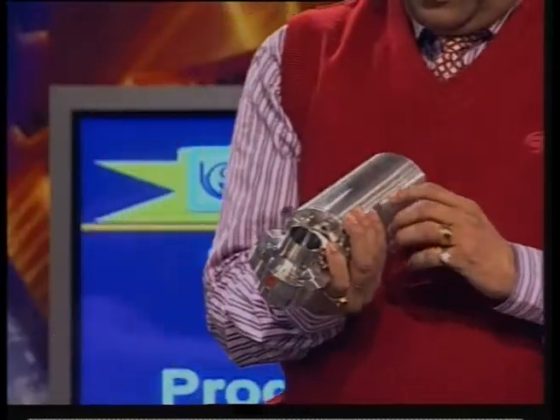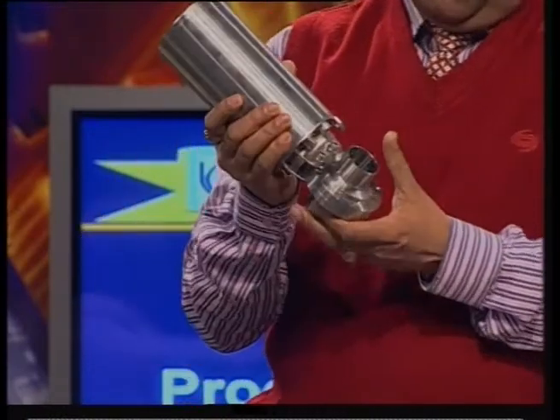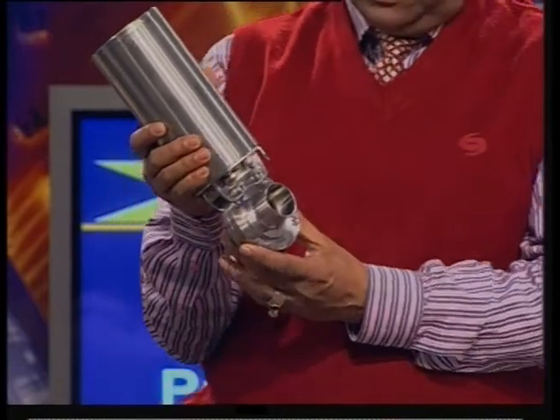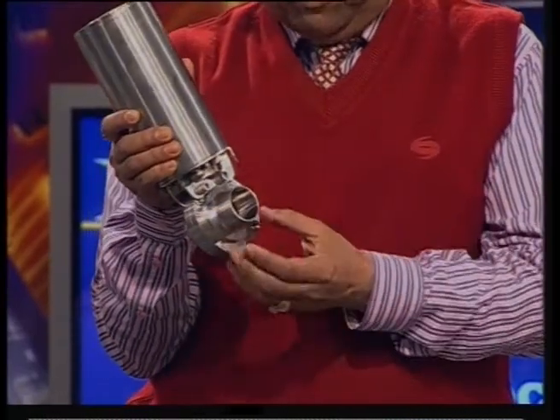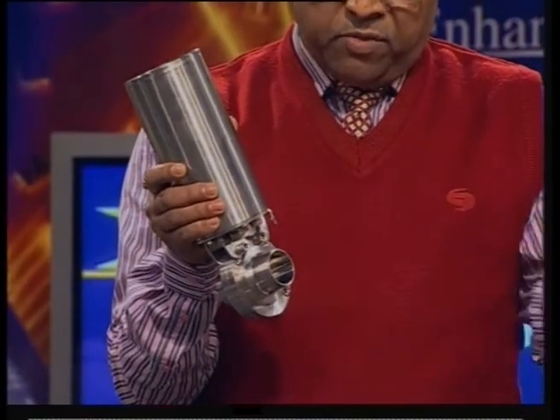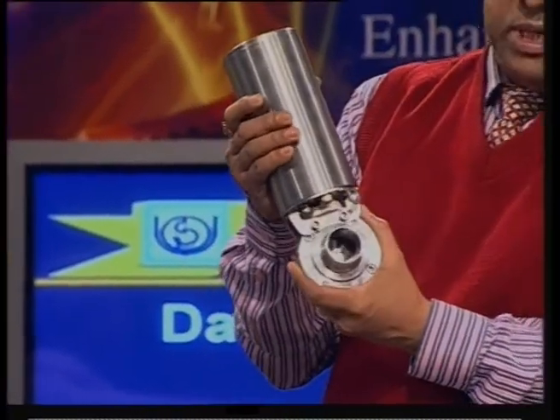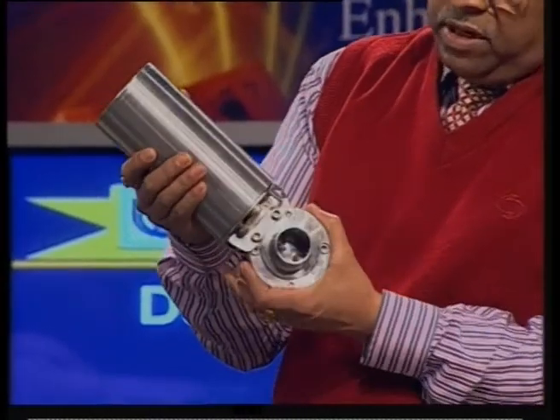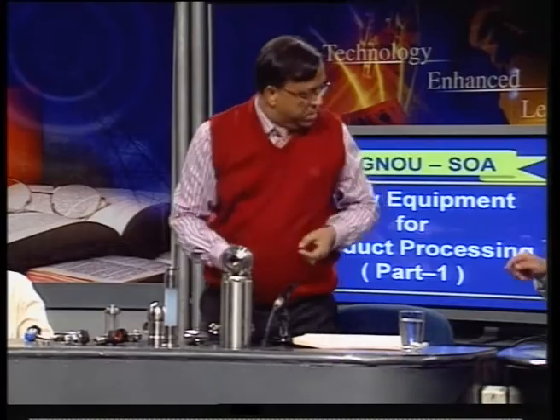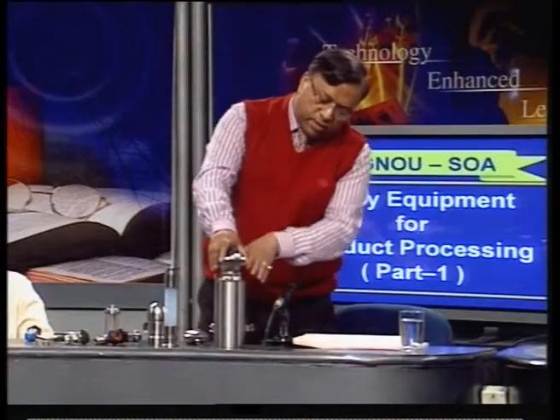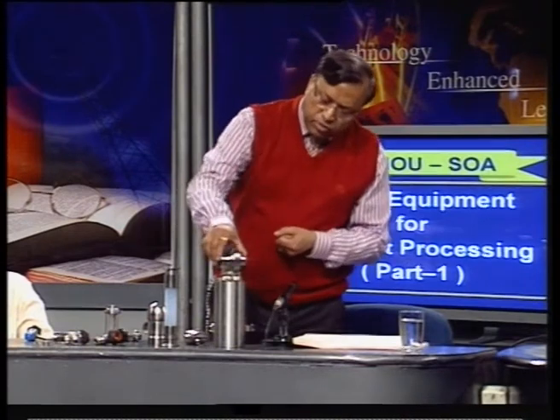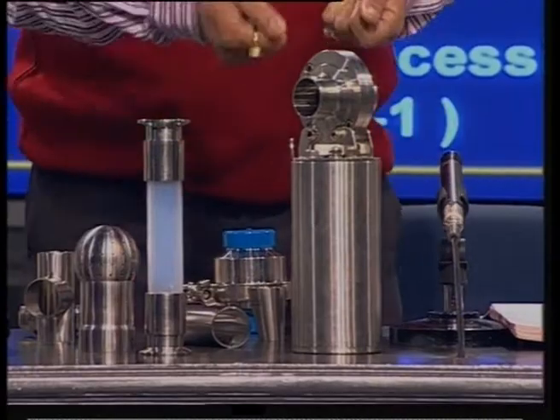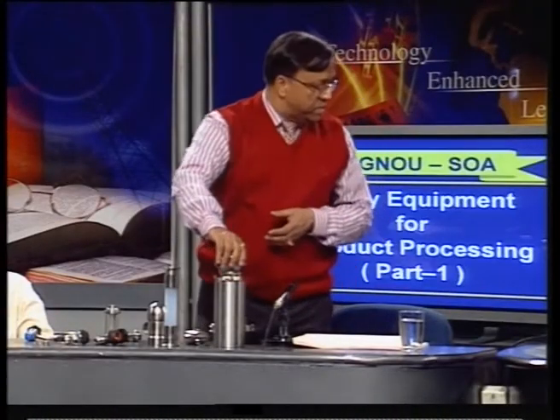Butterfly valves are used in every application in the dairy industry. Earlier we used to have plug valves; nowadays they are more or less replaced by butterfly valves. They are maintenance-free and you can use them from the reception to the milk powder section — for liquid milk lines, CIP lines, and all product application lines. You can have a handle or an actuator. If there is an air problem, you can remove the actuator in two minutes, put the handle, and operate it — no need to replace the total valve. This flexibility of the butterfly valve is a key advantage.